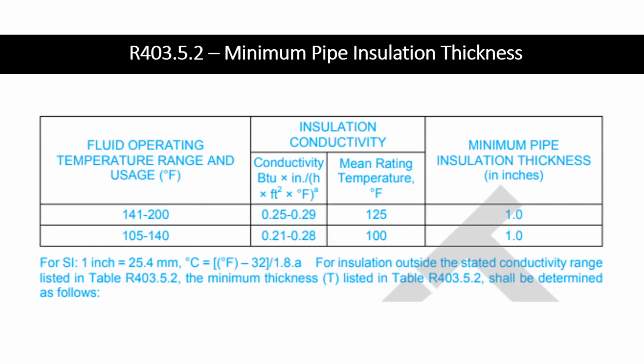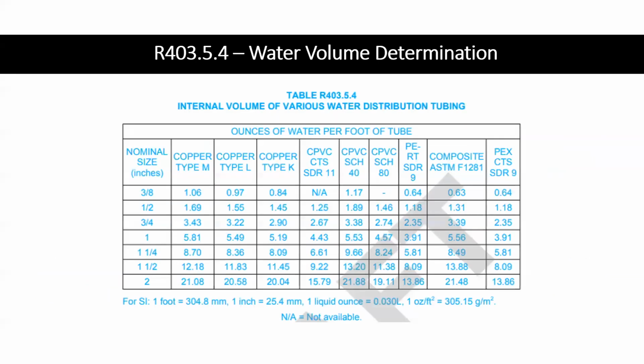This may change in the future, but right now it looks like they have the same requirement for both temperature settings. You just have to have that per 1 inch, but it's also doing the conductivity and then the rated system on that. If you read part of that, it talks about the minimum thickness. You also need to look at a different table on the thickness that you need, but it's just talking about the insulation thickness in inches for that. So just 1 inch for that part of it.